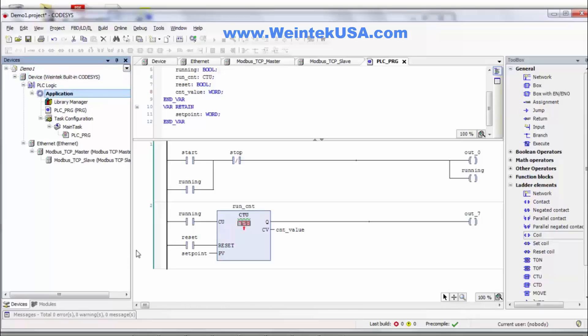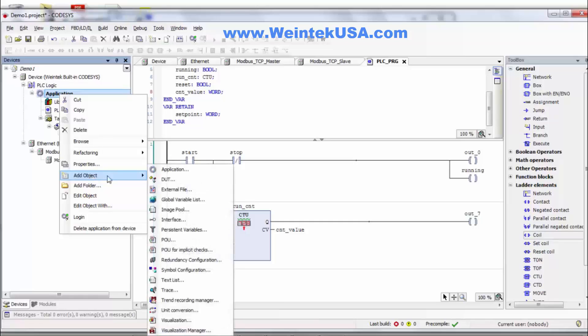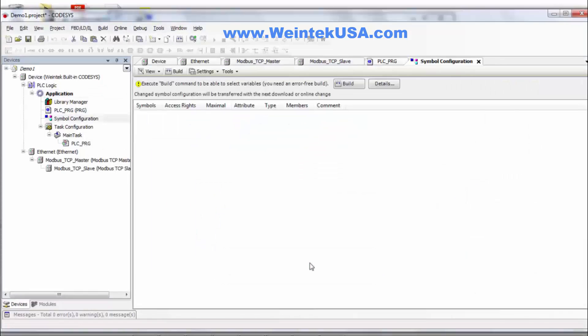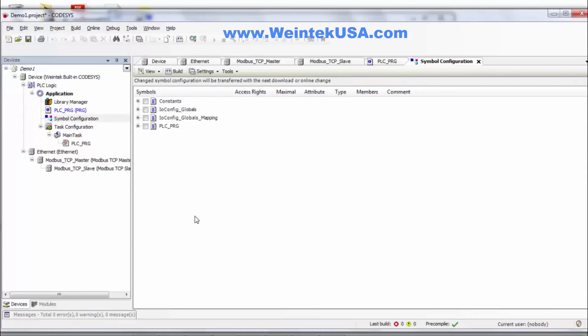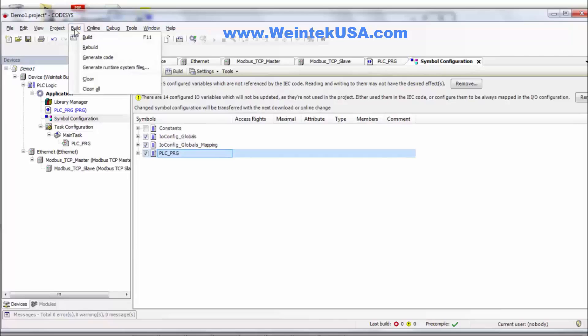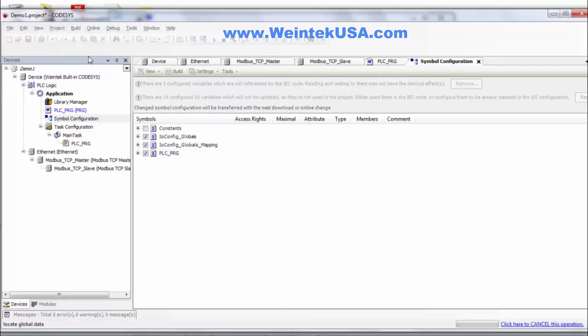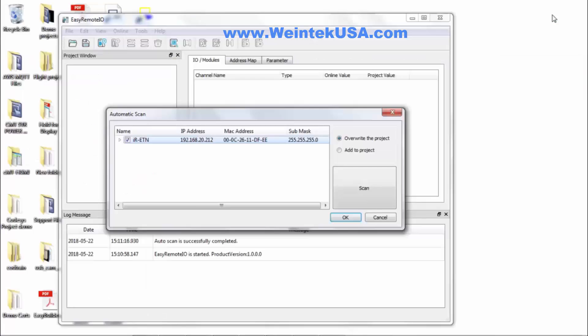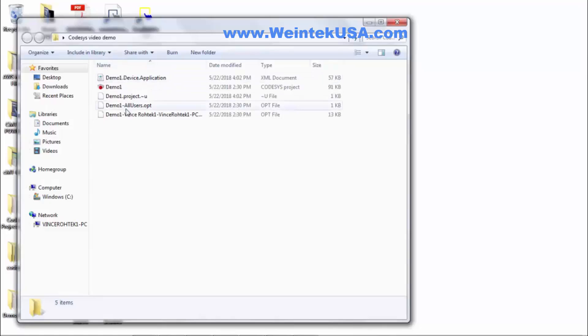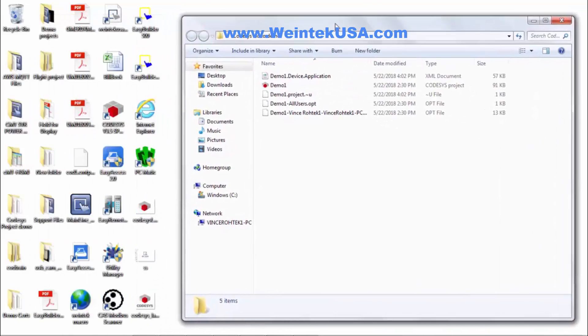So now we've got some objects here in our project defined so we can bring those on into our HMI project. Let's see how to do that. What we need to do is go to application and we need to add an object and we want to add a symbol configuration. That's good enough right there. Go ahead and hit build. And now you can see all our stuff here. We want to go ahead and select these three items and we'll go to our build tab here and we want to click generate code. Now if you remember the file we made, you'll see there's an XML file in here and we're going to use that. We're going to bring that into our project for our CODESYS tags and our EasyBuilder Pro project.